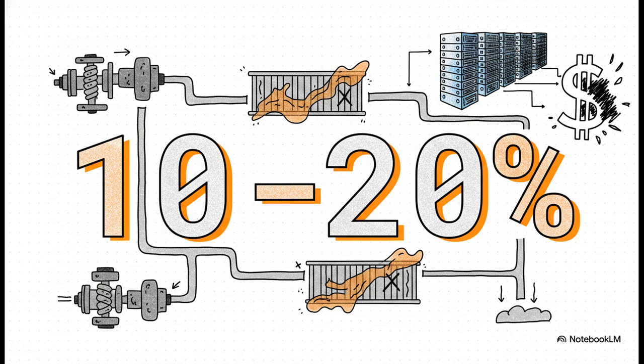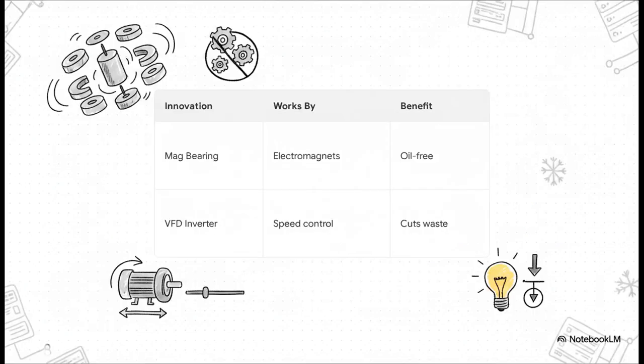Historically, there was a major bottleneck here. Both screw and centrifugal compressors needed lubricating oil, so their metal parts wouldn't just grind together. But that oil wouldn't stay put. It mixed with the refrigerant, traveled through the pipes, and coated the heat exchangers in this thin, slimy layer, which absolutely crippled heat transfer, dropping system efficiency by an incredible 10 to 20%. In a massive AI facility, a 20% drop translates to millions of dollars in wasted electricity. Literally millions. So the industry fought back with two game-changing technological upgrades.